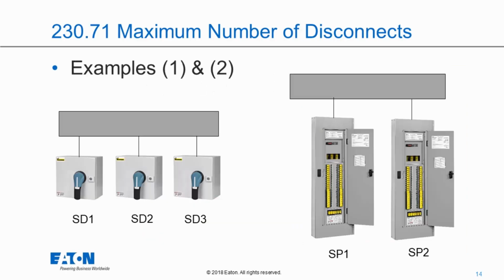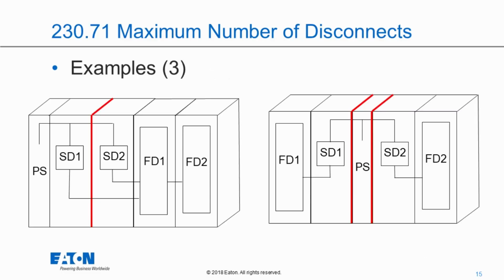If we look at examples 1 and 2, here we have an example for separate enclosures on the left, and we come into a trough probably, and then we tap off into each service disconnect. Of course, those service disconnects would have to have those line side barriers. That's required per 230.40. And then we also look at this example of number 2. Here we come into a trough, and we go to 2 separate panel boards, each with their own service main.